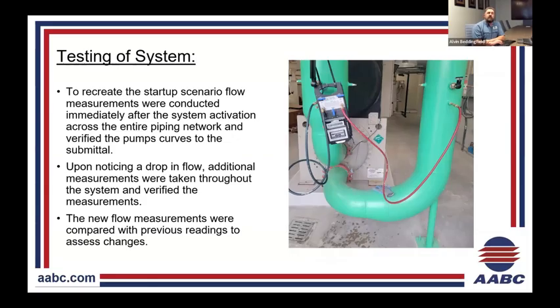To recreate it from startup, as I said, we let the system shut off and settle out, took pressure measurements, started up the condensing water system, and took measurements across the chiller, across the pumps, strainers, anything we could take a measurement across, just to try to figure out where the flow is. That way we can plot the chiller manufacturer's submittal flows and plot across the pump curves, just trying to get a snapshot of what happens right when it starts.